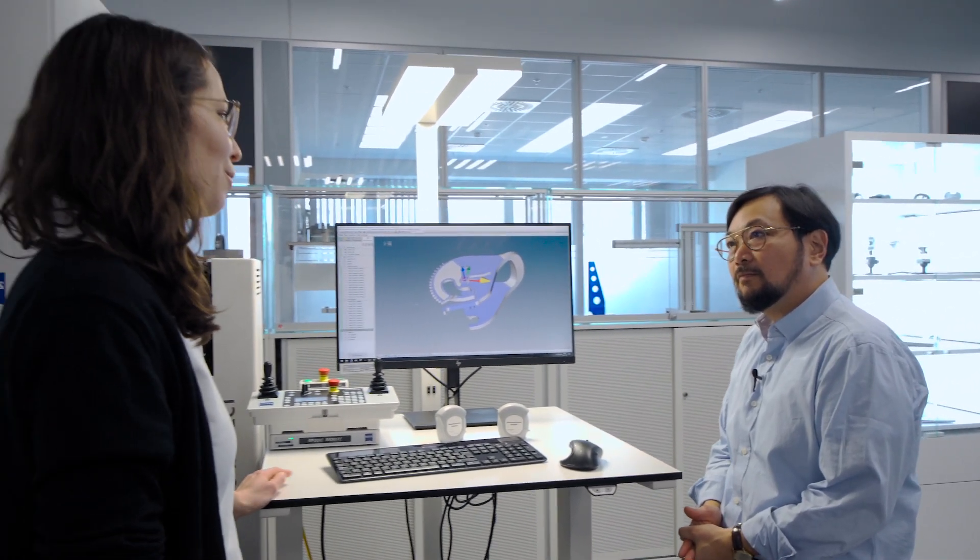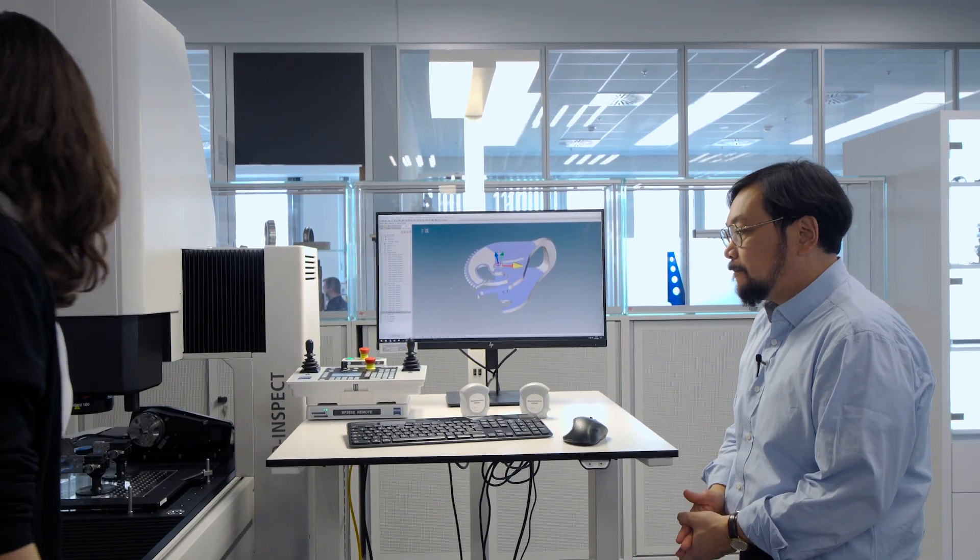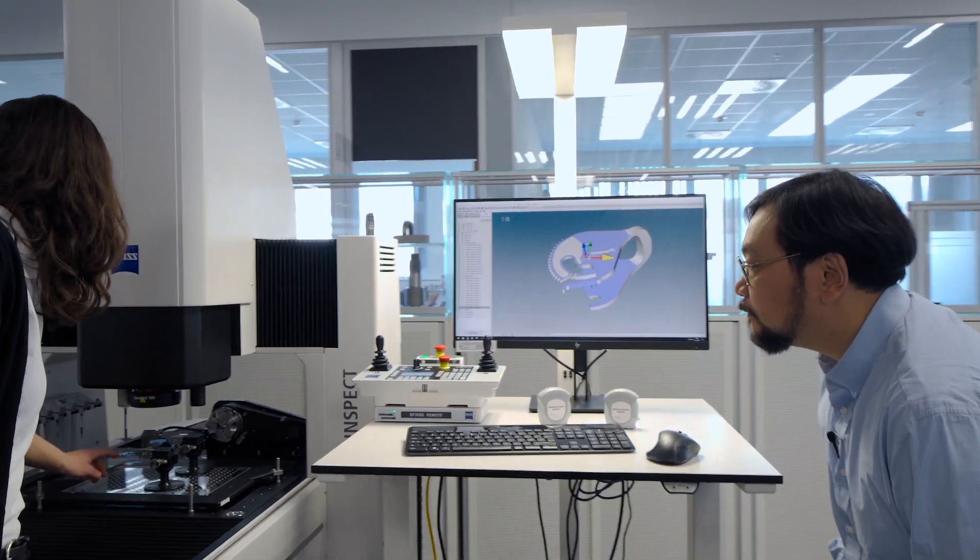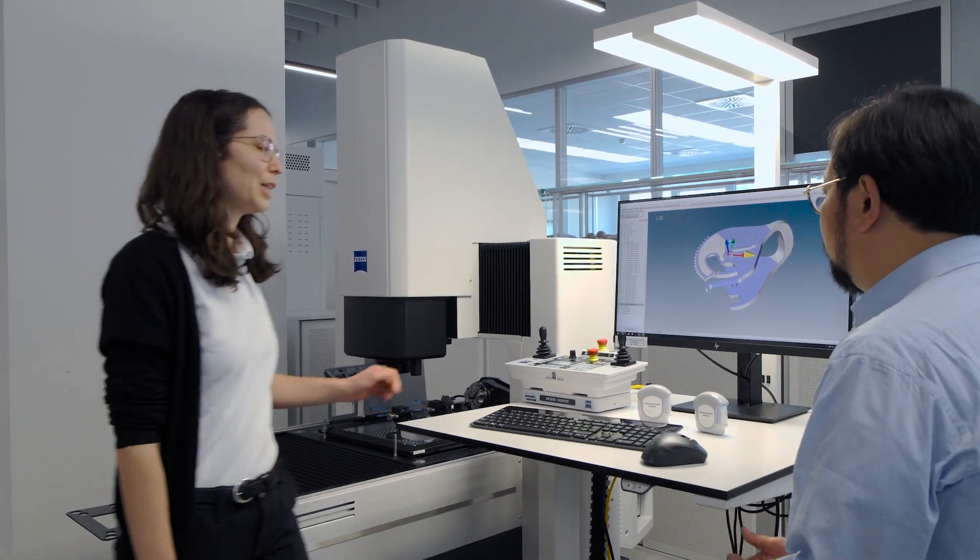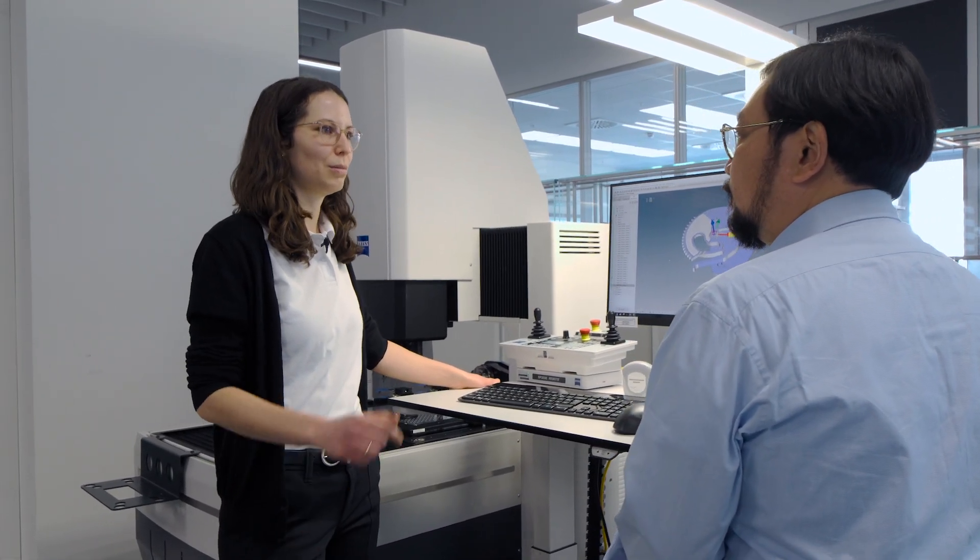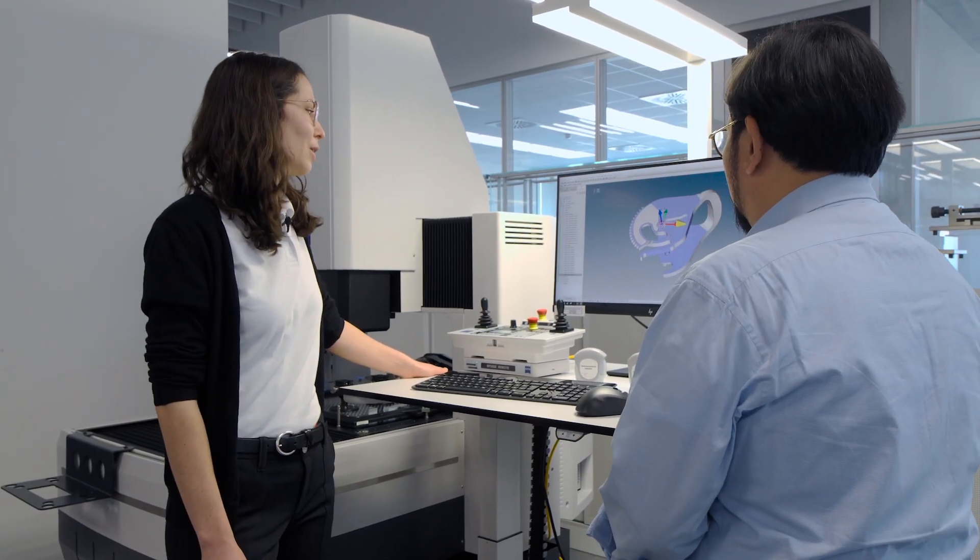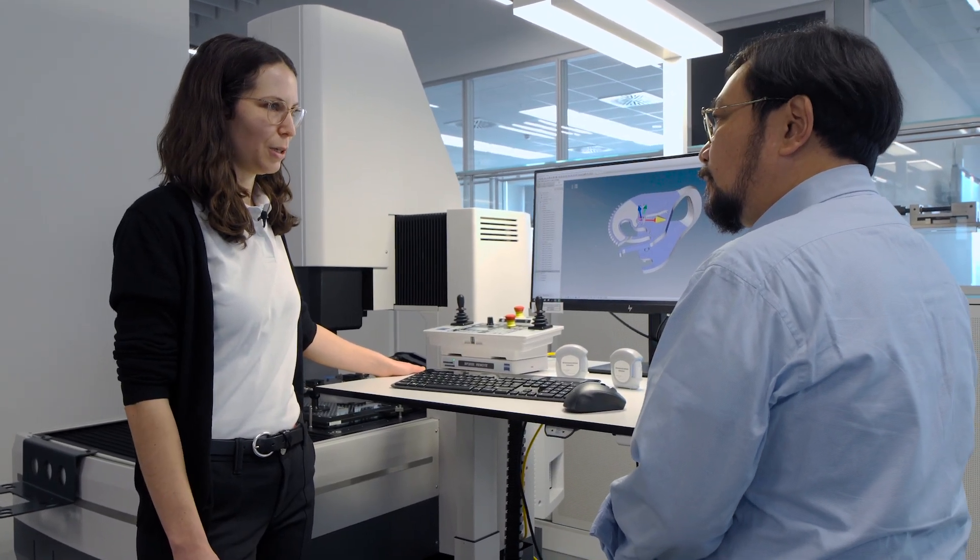So, medical plastic parts are often very thin and flexible. Sure. Also, that one here, you can see that area is quite flexible. And if you would touch that area with standard probing force, it could be deformed by touching. Sure. And that would lead to wrong results, of course.